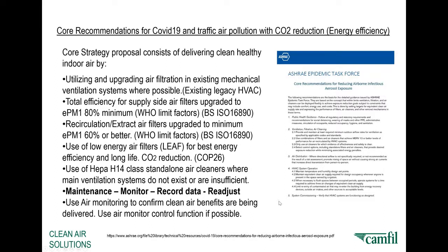It's all very good actually, apart from the MERV ratings, which unfortunately ASHRAE 52.2 is not quite up to date with ISO 16890, which is a current world standard, which should be used as its methodology is very much up to date with the latest accurate measuring methods.